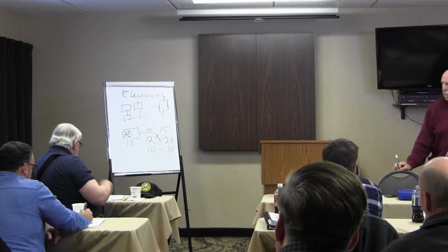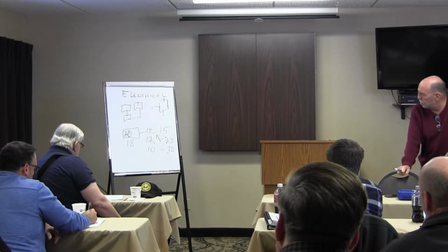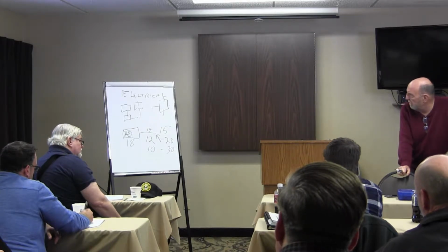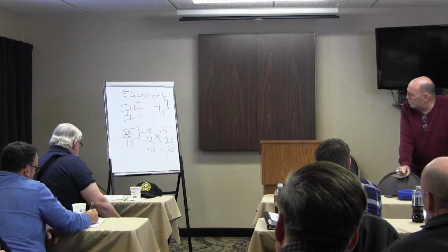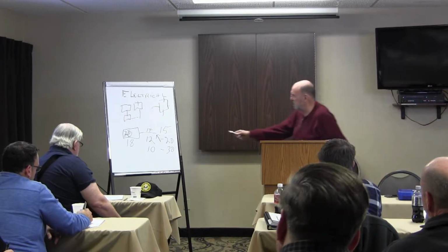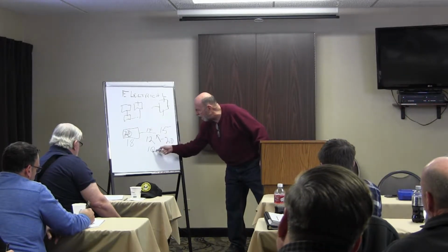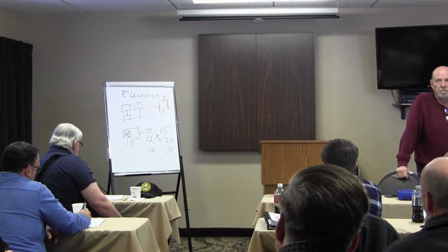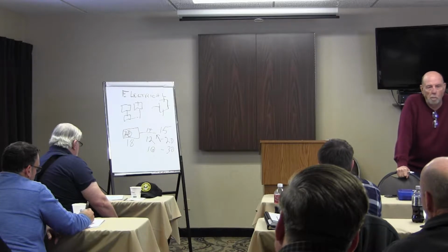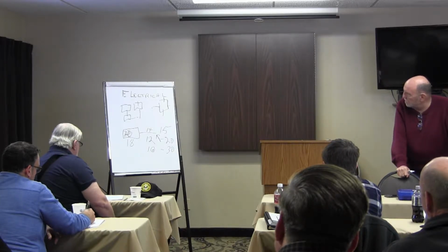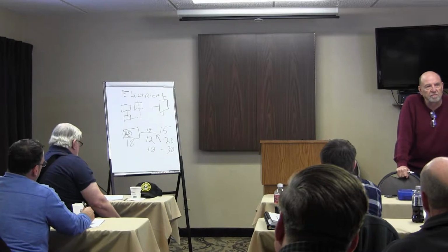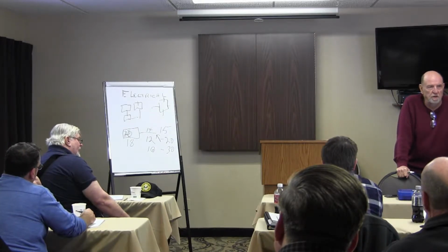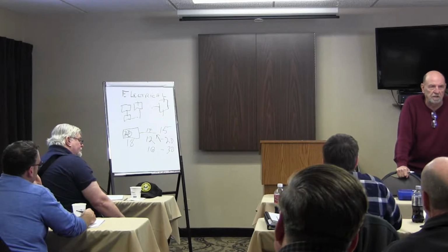Jason? Yes. What happens when I put 15 amps through this 10 gauge wire? That's the wrong wire for that breaker. What happens, Jason? Nothing. Very good, thank you. That was simple. What happens when that 30 amps is going through the 14 gauge wire? It's going to catch fire. Well, it's going to heat up and it's going to cause a fire in something.